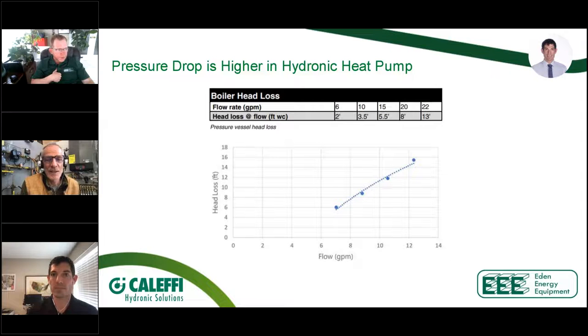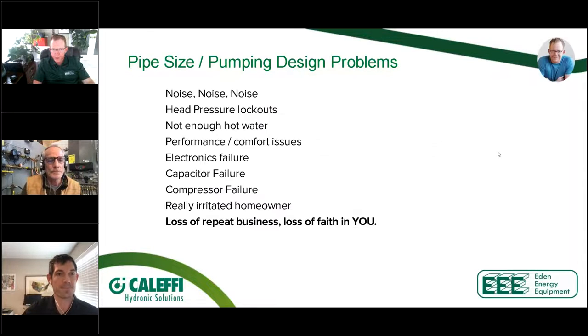Yeah, I guess the good news if you do have those high head situations is now with the ECM pumps, we're not using 200 watts anymore to run a high head pump. We're using maybe 100 watts. So we can get that out a little bit more efficiently with the ECM technology. So hopefully everybody's embracing those pumps when they do these designs, because that's another energy saver. Yeah, 100%, 100%.